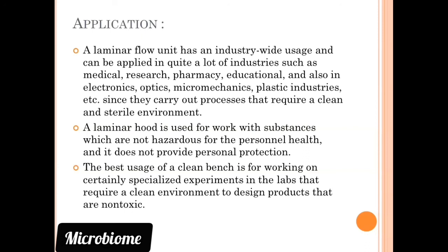A laminar hood is usually for work with substances which are not hazardous to personal health, and it does not provide personal protection. The best use of a clean bench is for specialized experiments in the labs that require a clean environment to design products that are non-toxic.